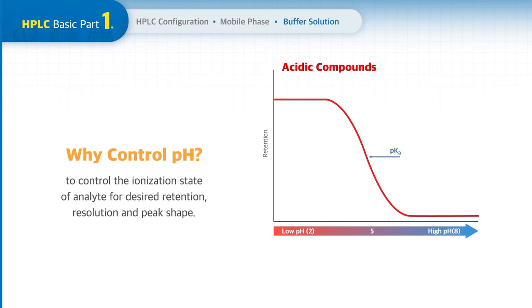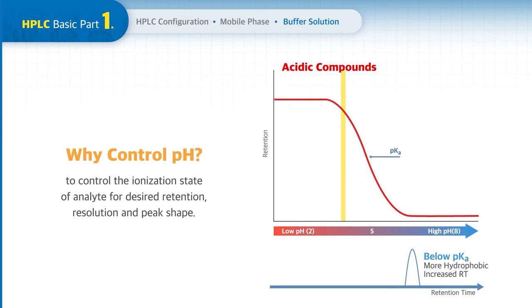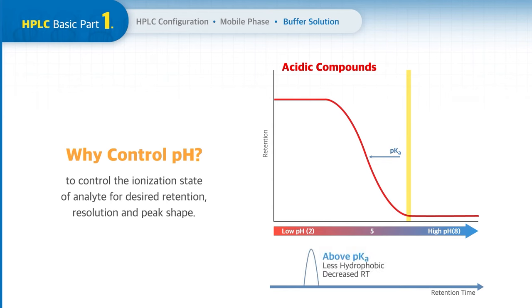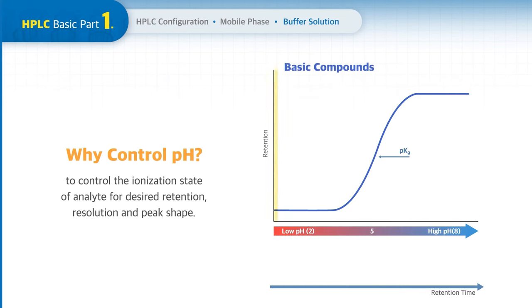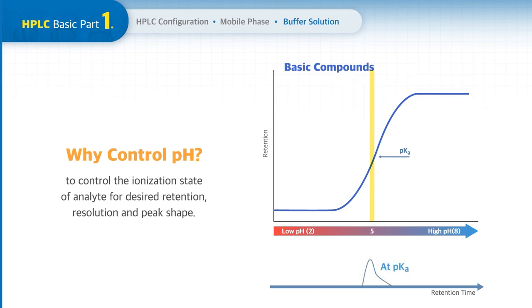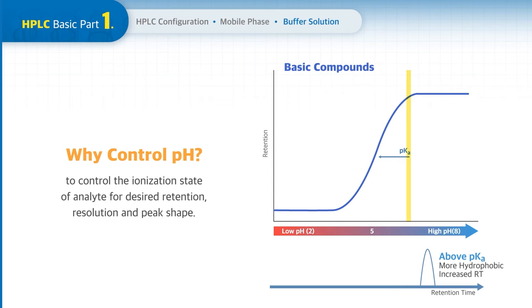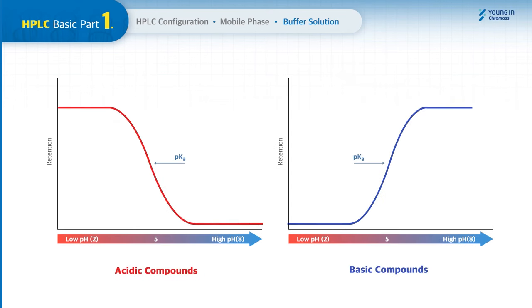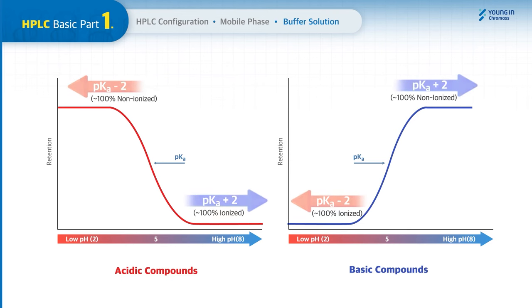For acidic compounds, if the pH is below the pKa, the analyte becomes more hydrophobic and is retained longer. At the pKa range, small changes in pH lead to large changes in retention and resolution. If pH is above the pKa, the analyte becomes less hydrophobic and elutes faster. For basic compounds, it works vice versa. The most important rule is that the pH of the mobile phase must be at least two units above or below the pKa value for maximum analyte stabilization.